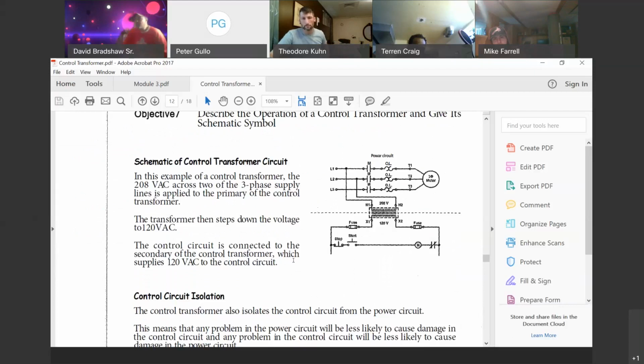Remember when I told you I like to always go up and wire my high voltage first, then come back and do my control circuit? Because there's a button I can push manually to make sure my motor turns. So if my motor turns, you probably got like 75 or 80% of that circuit built.